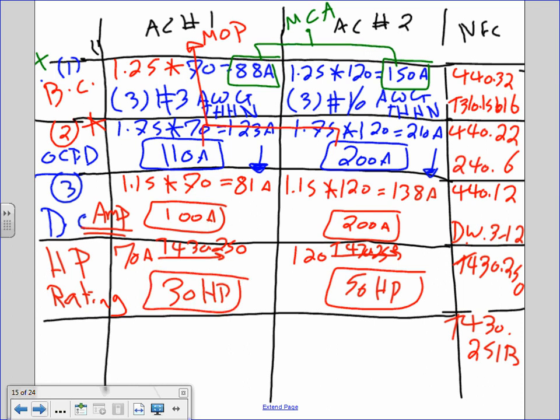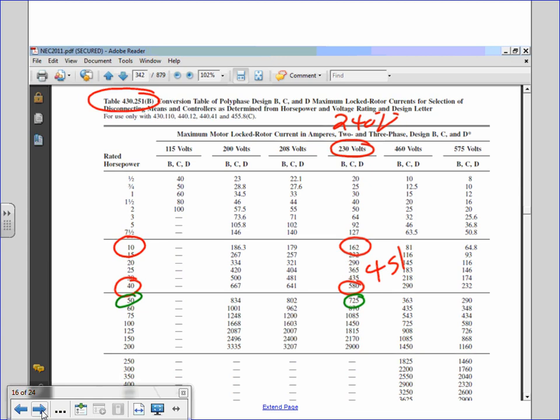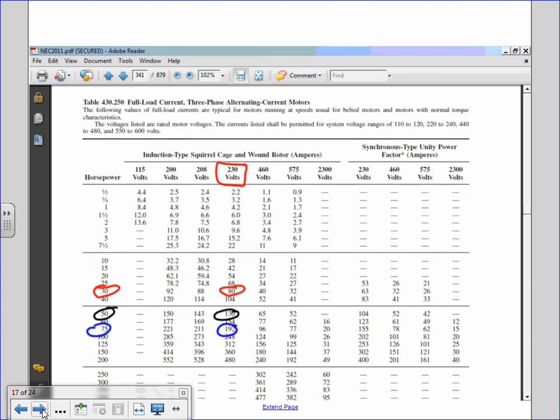In Table 430.250, at voltage 240/230, look up full load amp. For 70 amps — there's no exact 70, so between 68 and 80, go to 80 — that gives 30 horsepower. For 120 amps, go to the next value up, which gives 50 horsepower.